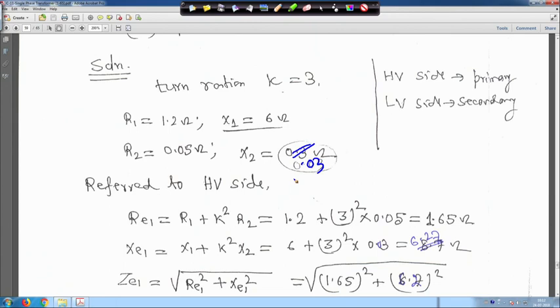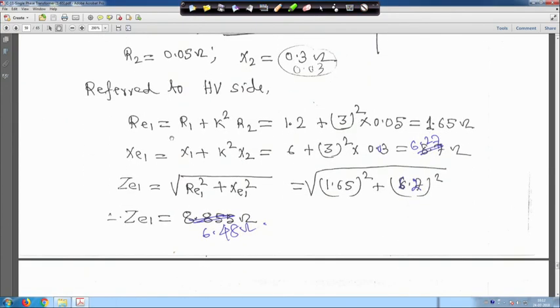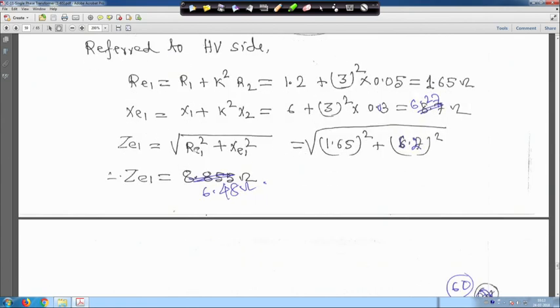Referring to the high voltage side: R_E1 equals R_1 plus k² R_2 = 1.2 + 3² × 0.05 = 1.65 ohm. X_E1 equals X_1 plus k² X_2 = 6 + 9 × 0.03 = 6.27 ohm. Impedance Z_E1 equals root of (R_E1² + X_E1²) = 6.48 ohm.